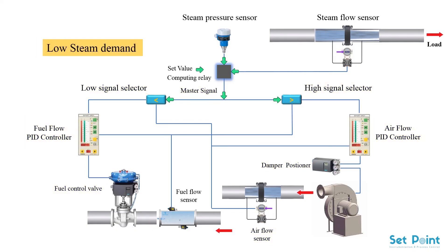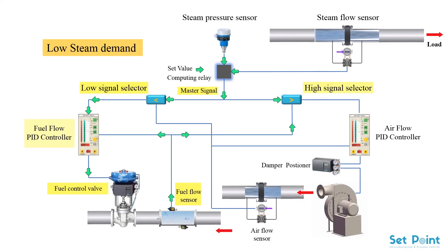When the steam demand is low, the low signal selector permits the master signal to the fuel flow controller. The fuel flow controller decreases the flow of fuel by adjusting the fuel valve. As the fuel flow decreases, the fuel flow sensor transmits the signal to the high signal selector and the fuel flow controller. The selector then sends the master signal to the air flow controller to decrease air flow by adjusting the damper.